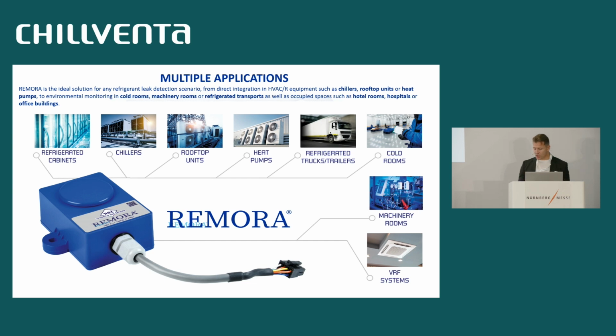In terms of application, this is extremely flexible. It can be installed in refrigerated cabinets. It is aimed to be installed directly inside HVAC or refrigeration equipment, inside the unit: chillers, rooftop units, heat pumps. It can be installed inside refrigerated trucks or trailers. It can also be installed in environments such as cold rooms and machinery rooms. It can be used in hotel rooms, office buildings, hospitals, to monitor also VRF systems.